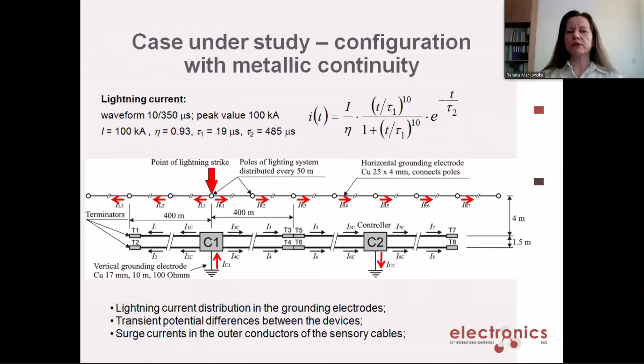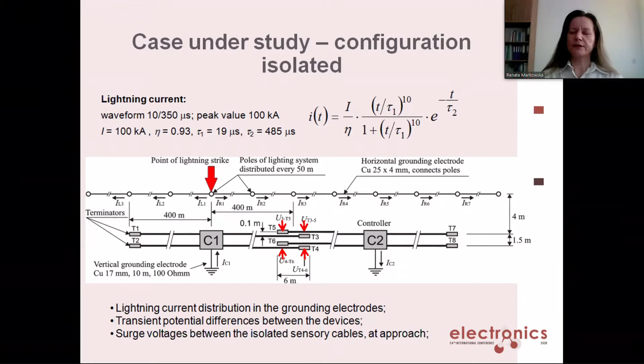For the configuration with metallic continuity, the following quantities have been computed: the lightning current distribution in the grounding electrodes, horizontal and vertical, the transient potential differences between the devices, and the surge currents in the outer conductors of the sensory cables. A very similar situation will occur in the isolated configuration, but in this case, the surge voltages between the isolated sensory cables at the places of their approach were calculated additionally.